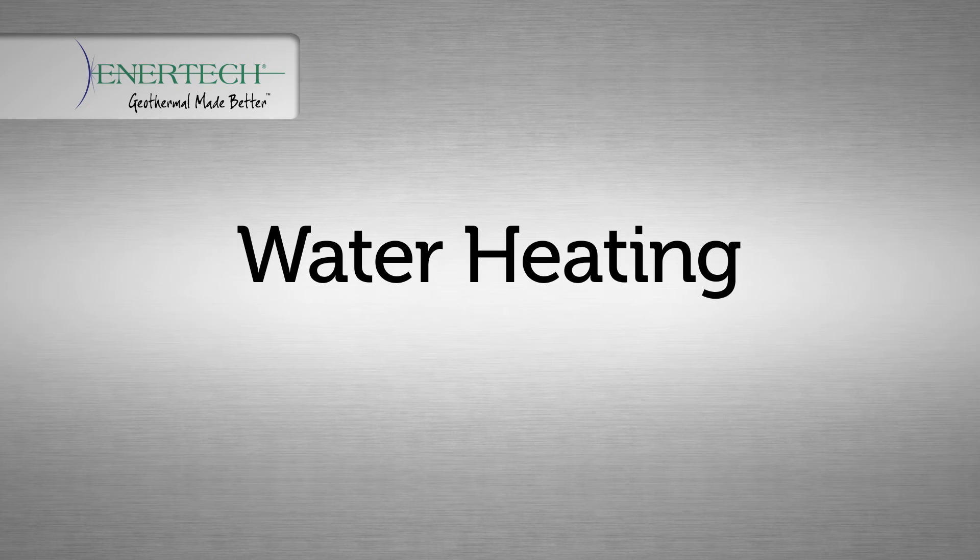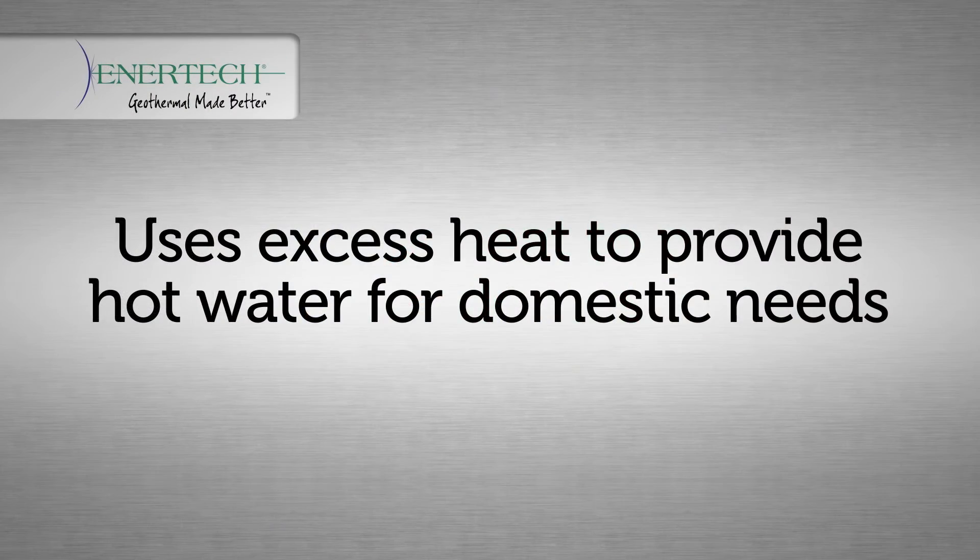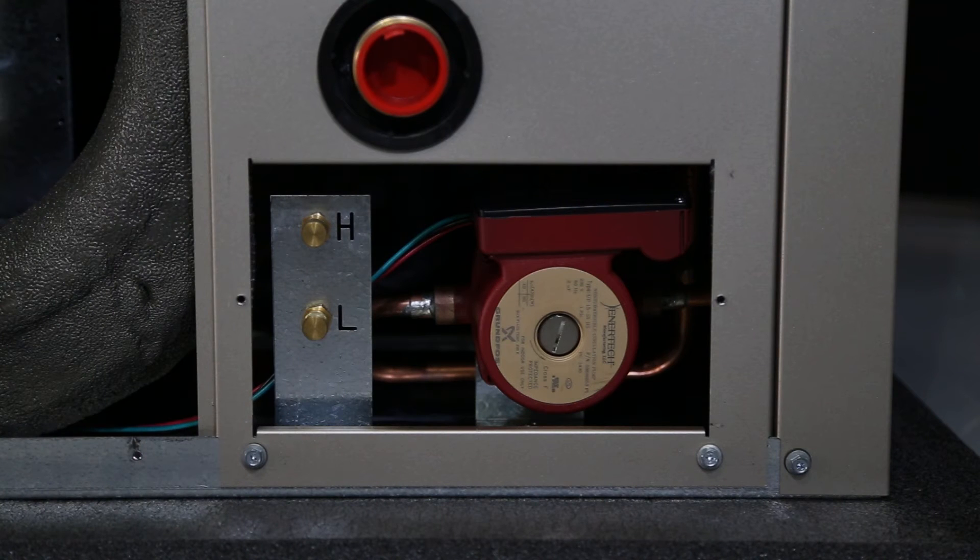Water heating is standard on all residential units. Units may be ordered without. It uses excess heat during both heating and cooling cycles to provide hot water for domestic needs. A double wall desuperheater coil exchanger is located between the compressor and the reversing valve. It extracts superheated vapor to heat domestic water while satisfying its heating and cooling needs.